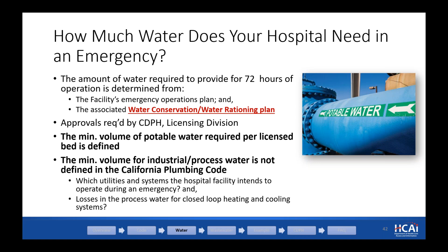Approvals are required by CDPH, which is the licensing division. Again, the minimum volume of potable water required per licensed bed is defined in the California Plumbing Code, but the minimum amount of industrial process water is not defined in the code. To come up with what amount of water is required there, we need to understand which utilities and systems the hospital facility intends to operate during an emergency, and also the losses that happen in the process water for closed loop heating and cooling systems. There are evaporation losses, and from what I understand, blowdown, which happens every so often. So we work with the mechanical engineer to figure those out.